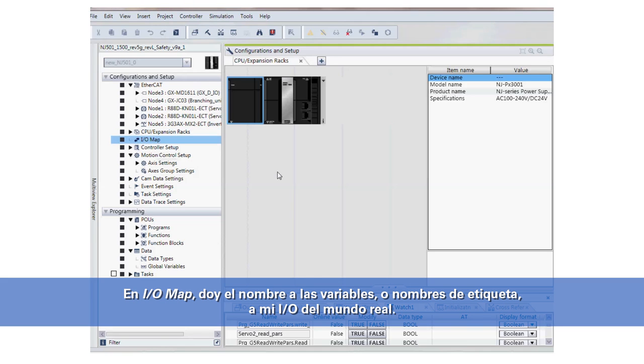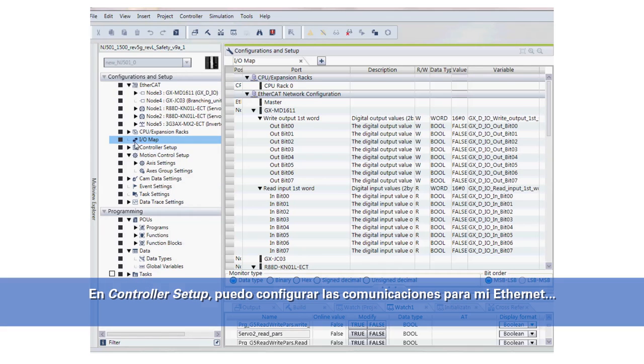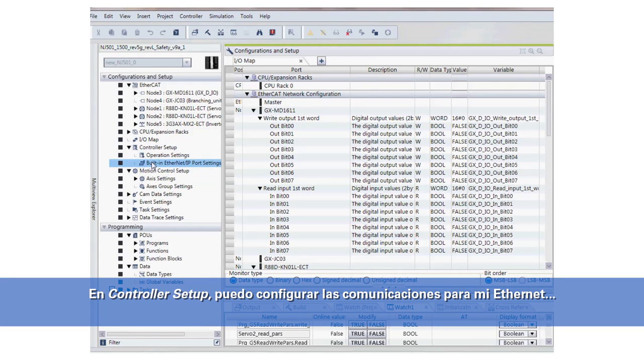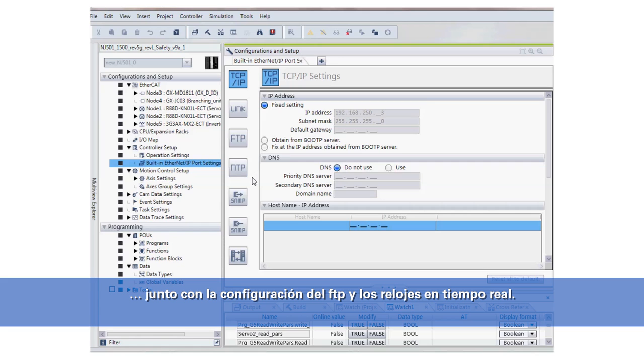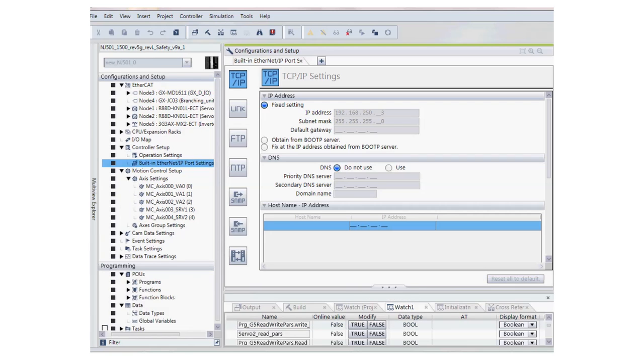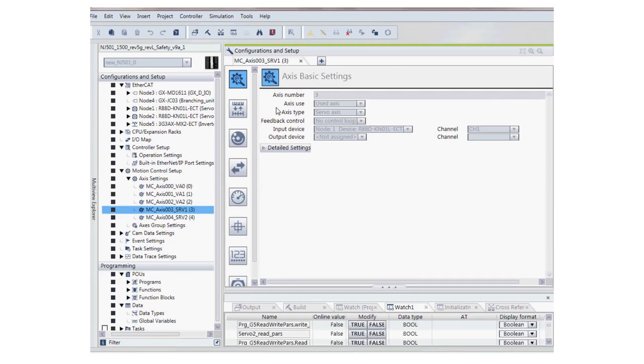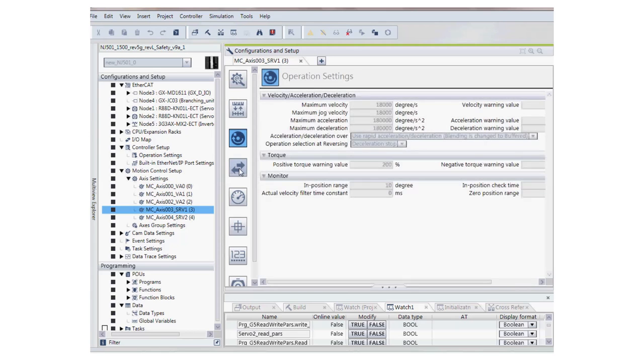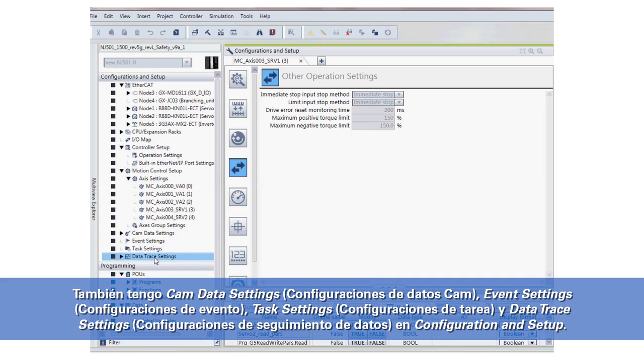Under I/O map, this is where I give the variable names or tag names to my real-world I/O. Under controller setup, this is where I can set up the communications for my Ethernet, along with setting up FTP and real-time clocks as well. Under the motion control setup, this is where I'll set up my servo motors. I also have CAM data settings, event settings, task settings, and data trace settings under configuration and setup.